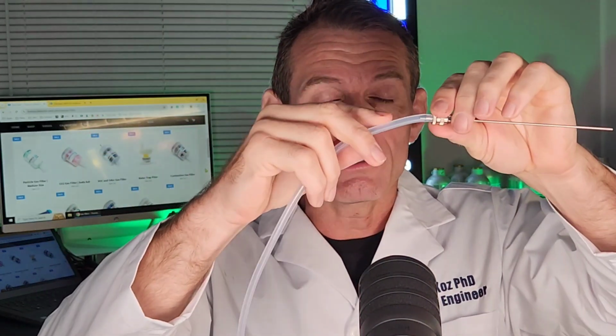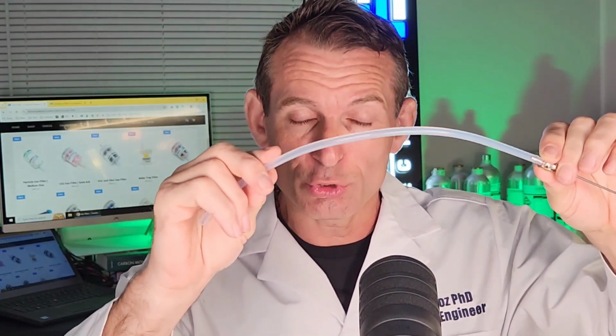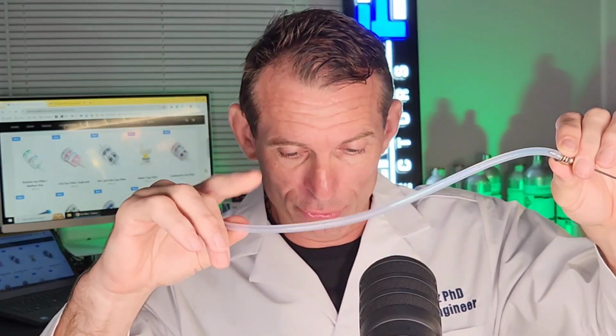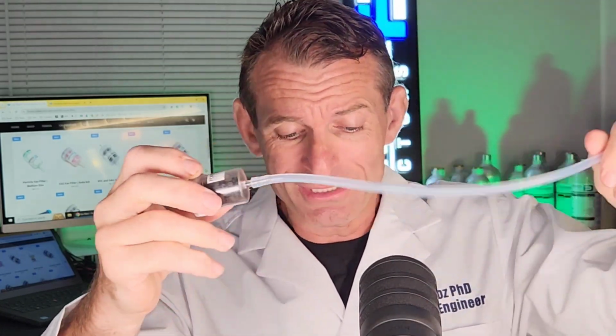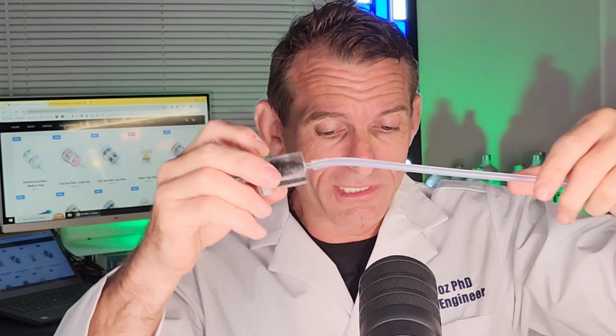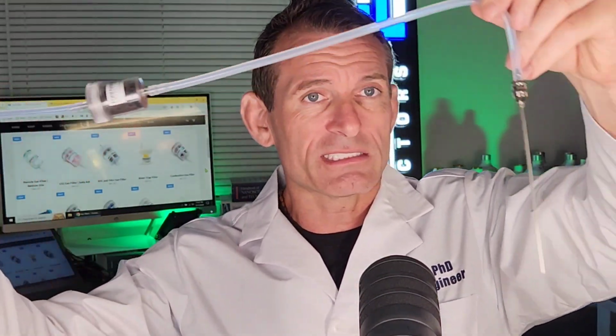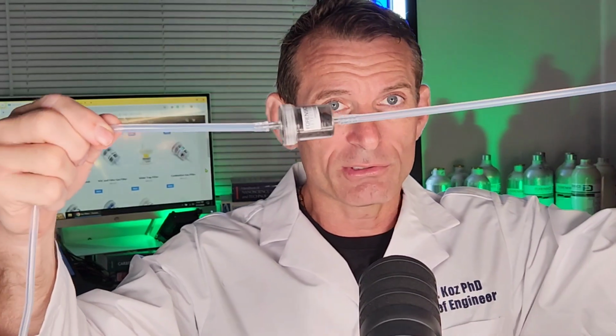That's the point. Then we are using in all our products, Dr. Koz emphasizes high temperature flexible silicone tubing like so. This is our 1/8 inch tubing, roughly 3 millimeter internal diameter tubing, and in line we may need to use a filter. So we just pop it on, and all our filters are barb fitting, so it's easy to use the tubing and cut them shorter, cut them longer, and to put it in line with your analyzer. Then get your other piece of tubing, and then we are in line with the gas sample. So we have our probe, our intake, the air goes through the filter, then through the second piece of tubing, and then it ends up in our gas analyzer, folks.